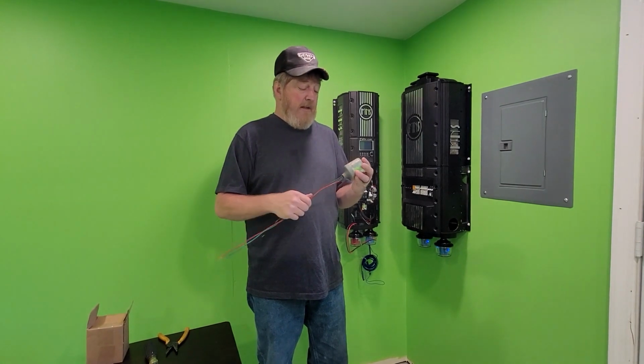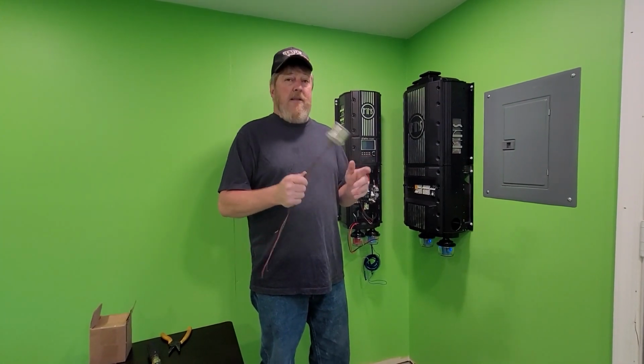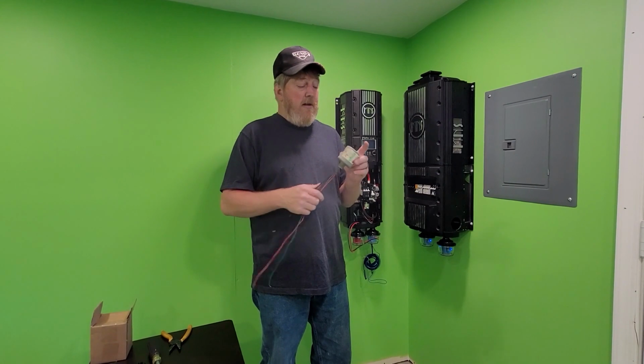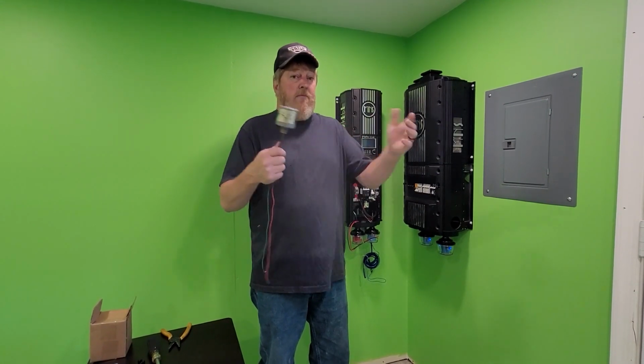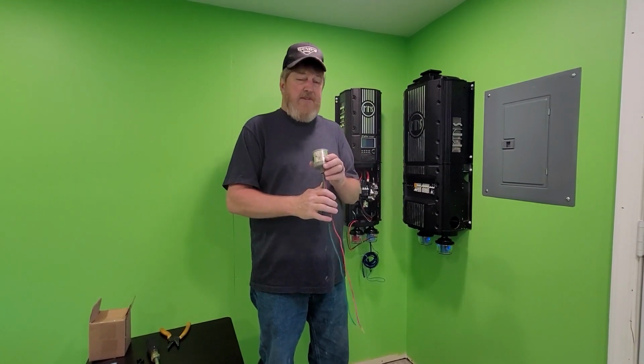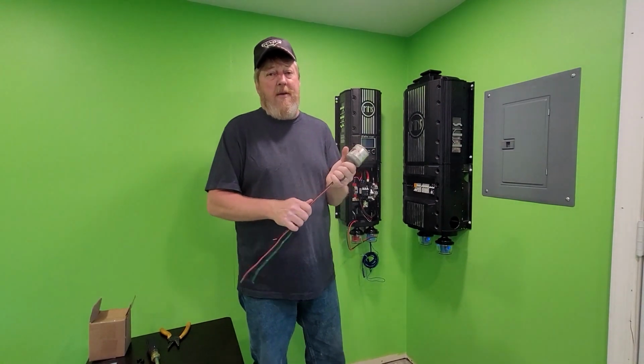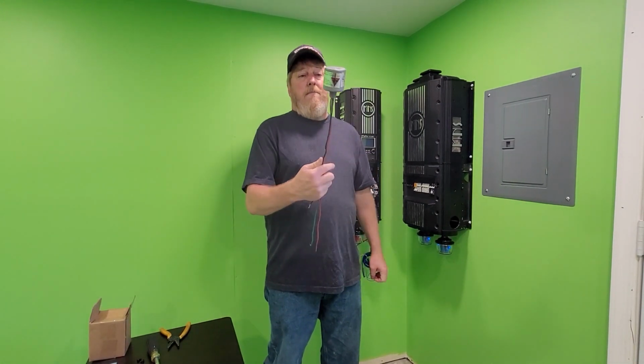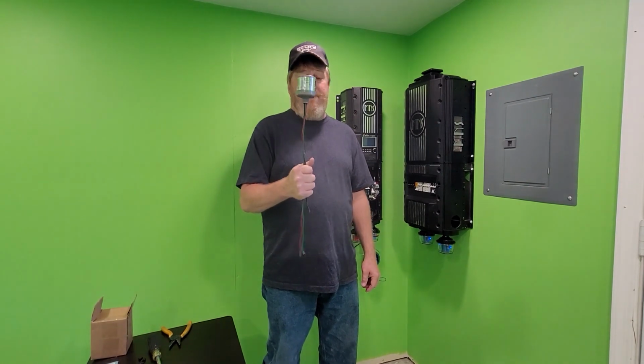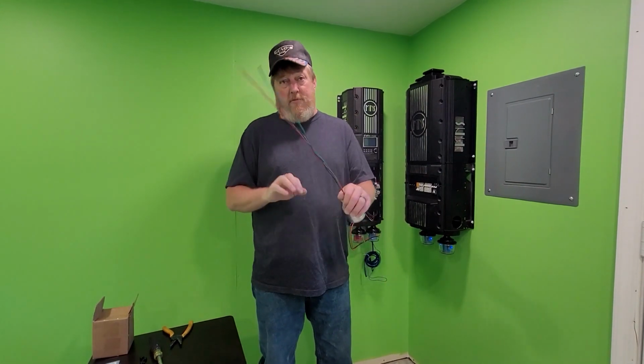Well, I shouldn't say they do absolutely nothing - we'll save that for the video - but they don't do hardly anything. They are an air gap instead of a surge arrestor, so they take tons of voltage to arc over, and by that time everything is blown up. If you're getting sold one of these by your distributor, you're getting the short end of the deal.